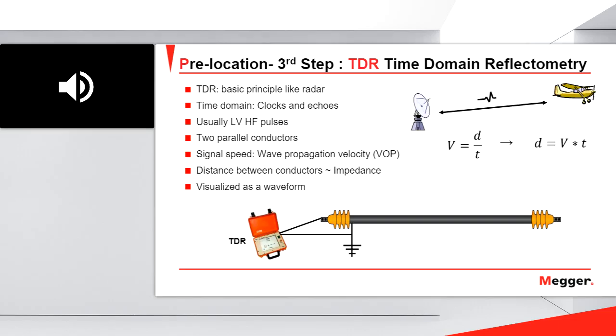The first thing that I will use is the TDR, the time domain reflectometer, and the operating principle of the TDR is pretty much the same as the radar at airports. Okay, when you have a radar at an airport, the radar sends a pulse. The pulse reaches the plane and goes back to the radar. And what the radar measures is the time it took for the pulse to go from the radar to the plane and from the plane back to the radar. And if I know that time and I know the propagation velocity, in this case the speed of light, I will know the distance to the plane. Okay.